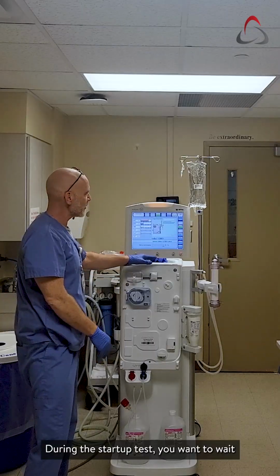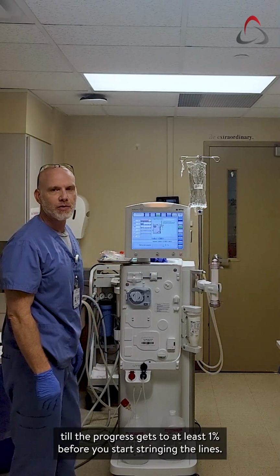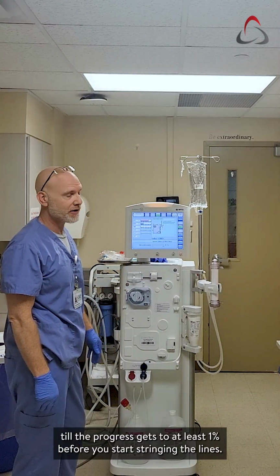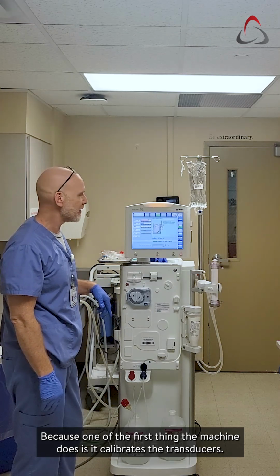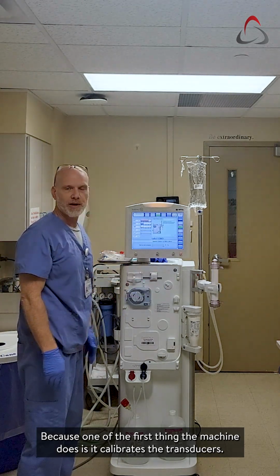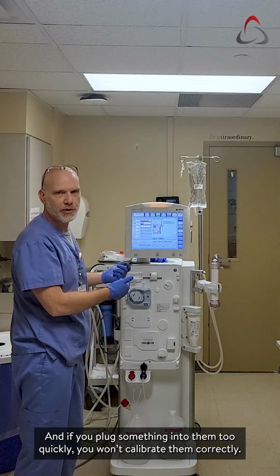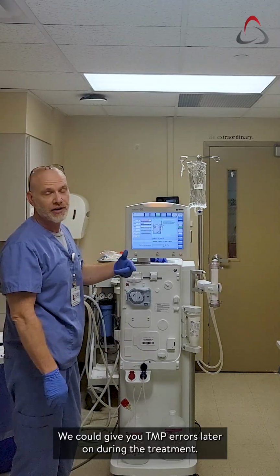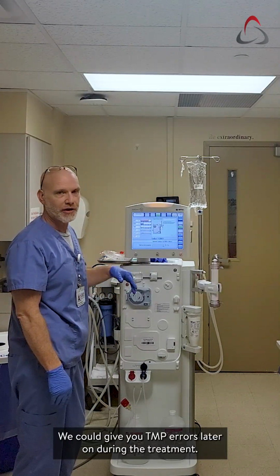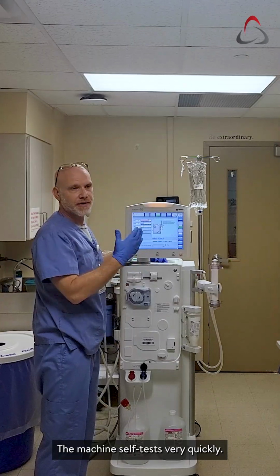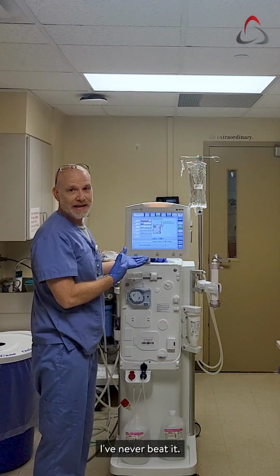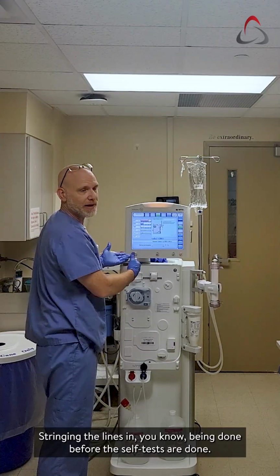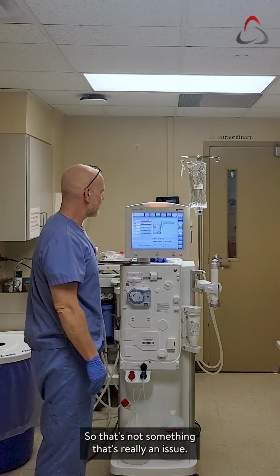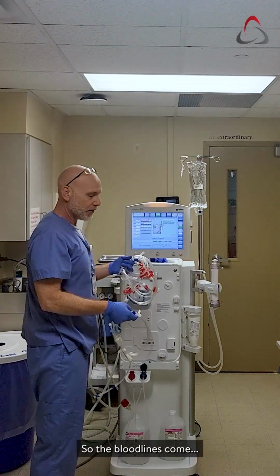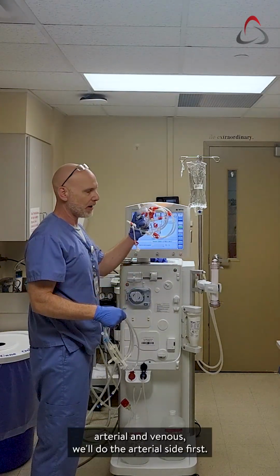During the startup test, you want to wait till the progress gets to at least 1% before you start stringing the lines, because one of the first things the machine does is it calibrates the transducers, and if you plug something into them too quickly, it won't calibrate them correctly. It could give you TMP errors later on during the treatment. The machine self-tests very quickly. I've never beaten it, stringing the lines and being done before the self-test is done, so that's not really an issue.